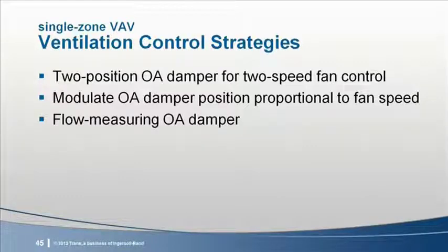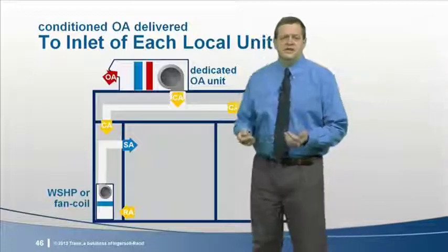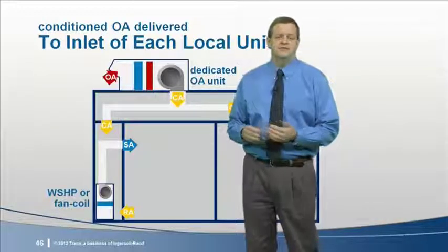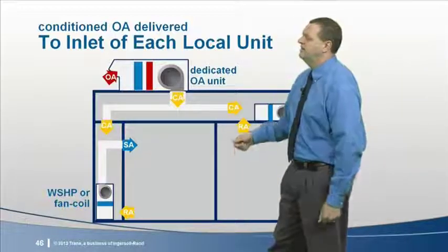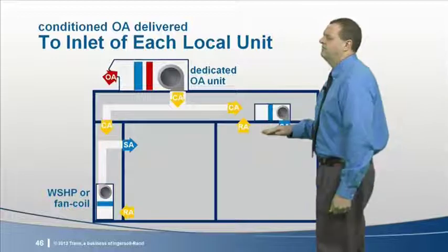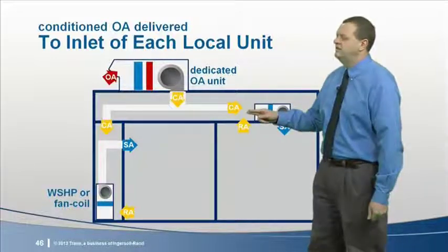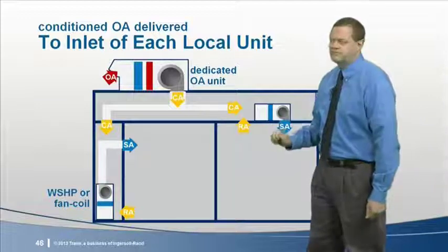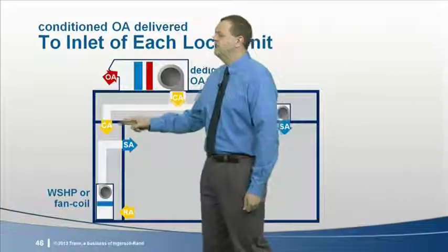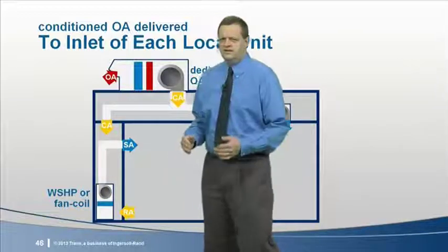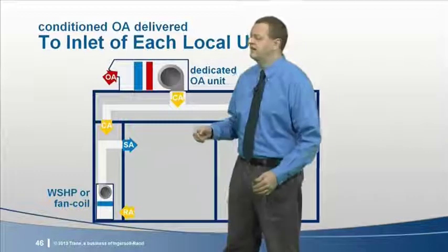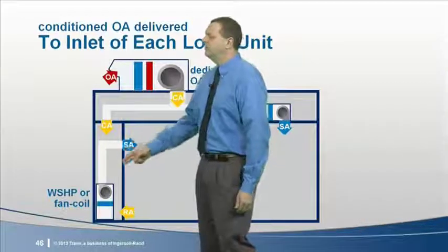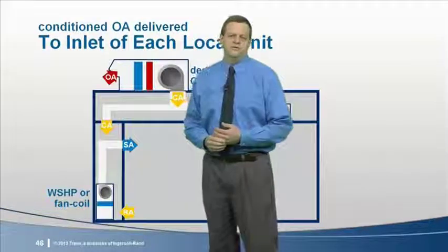But what about fan coils or water source heat pumps? Many models of that type of equipment just have a single inlet opening, no mixing box or outdoor damper. Ventilation is typically provided by a dedicated outdoor air system. In a lot of these applications, the dedicated outdoor system delivers the conditioned outdoor air to the inlet side of each local heat pump or fan coil. For a horizontal style unit, the air might be ducted to discharge into the open plenum near the unit's intake. For a vertical style unit, it might be ducted to a closet where the unit's installed. In either case, the outdoor air mixes with recirculated air in the plenum or in the closet before being drawn in to the local heat pump or fan coil.